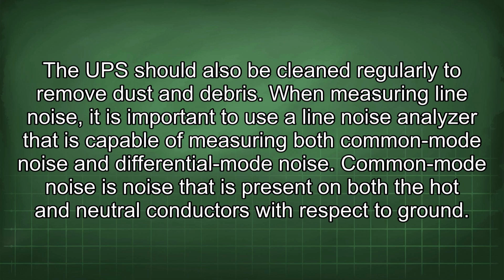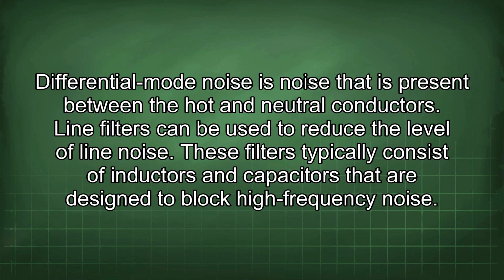When measuring line noise, it is important to use a line noise analyzer that is capable of measuring both common mode noise and differential mode noise. Common mode noise is noise that is present on both the hot and neutral conductors with respect to ground. Differential mode noise is noise that is present between the hot and neutral conductors. Line filters can be used to reduce the level of line noise. These filters typically consist of inductors and capacitors that are designed to block high-frequency noise.